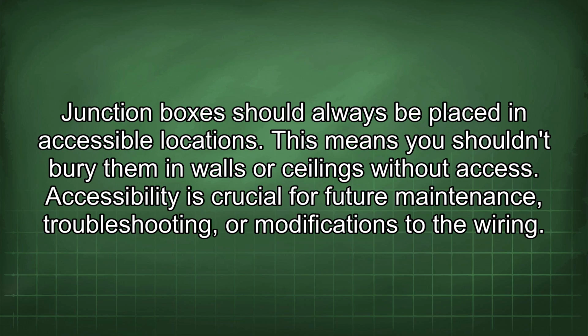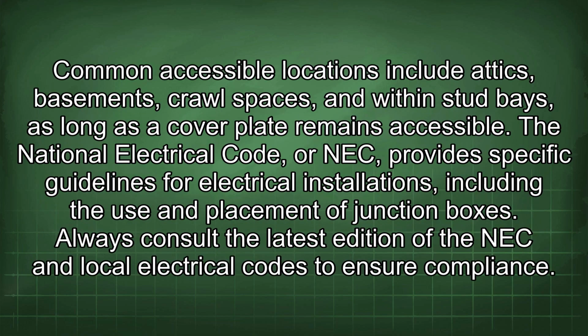Junction boxes should always be placed in accessible locations. This means you shouldn't bury them in walls or ceilings without access. Accessibility is crucial for future maintenance, troubleshooting, or modifications to the wiring. Common accessible locations include attics, basements, crawl spaces, and within stud bays, as long as a cover plate remains accessible.